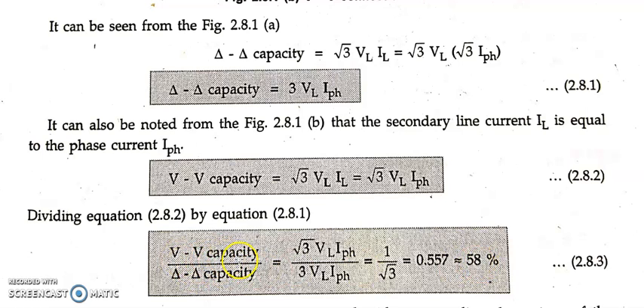So VV capacity, whatever it is in terms of kVA, will be equal to 58% of delta capacity. Yes, if I take delta capacity here, that is cross multiplication, then the kVA rating of VV capacity should be 57.7% or 58% of the delta capacity. That is what I told you. If a single phase transformer is of 1 kVA rating, then altogether the total capacity will be 3 kVA. So VV capacity equals 58% of 3 kVA or 57.7% of 3 kVA.